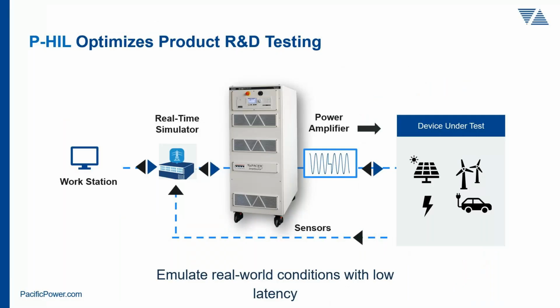The other feature we mentioned earlier is power hardware in the loop. It's very commonly used these days for microgrid simulations, where you want real-time simulation of interactions between a number of different energy resources connected to the same microgrid. This is done through a real-time simulator, which interfaces to the grid simulator through a high-speed analog interface, providing stimulus and response signals. It basically acts as a power amplifier in that context, but it requires a high-speed interface, not just a regular analog interface like you find on traditional grid simulators, but a very high-speed, real-time analog interface that is sometimes available on certain models as an option or standard. Very powerful capabilities in this kind of simulation environment.